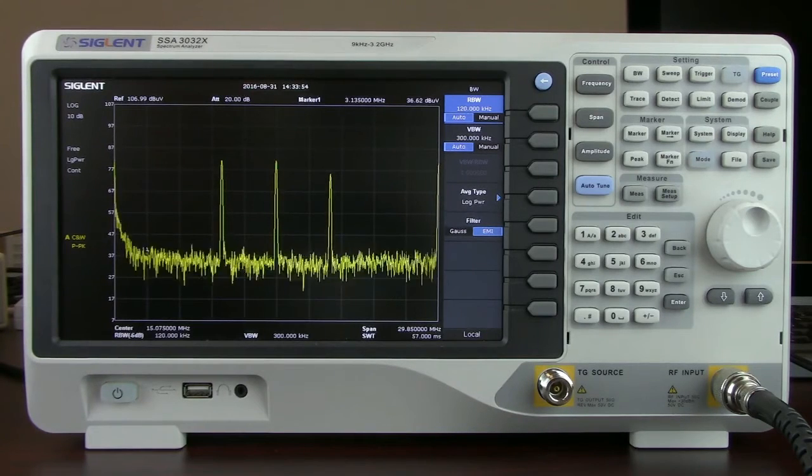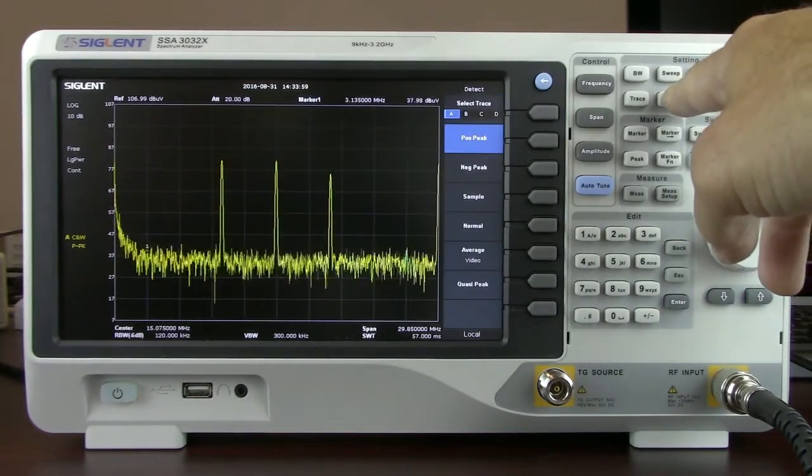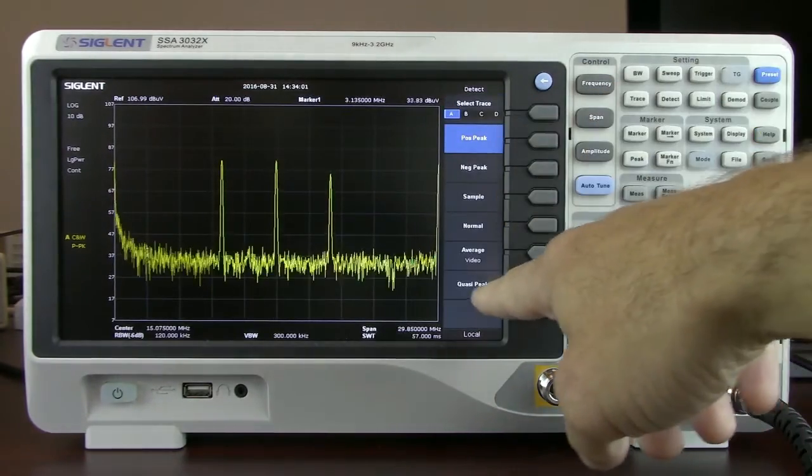We're also able to activate the quasi-peak detector. We can press detect and now you'll see the quasi-peak detector is available and we can select that.